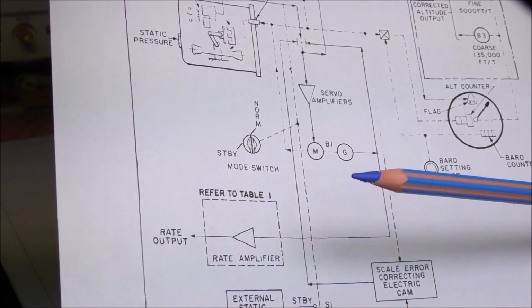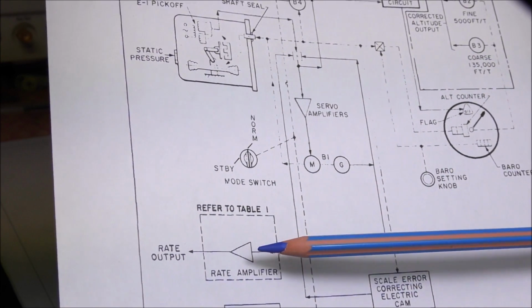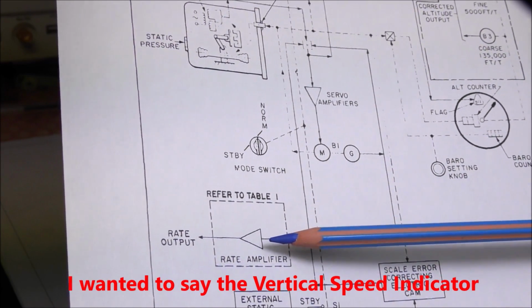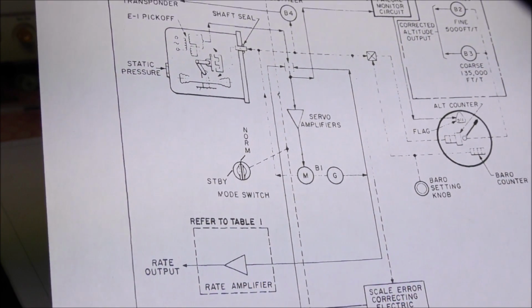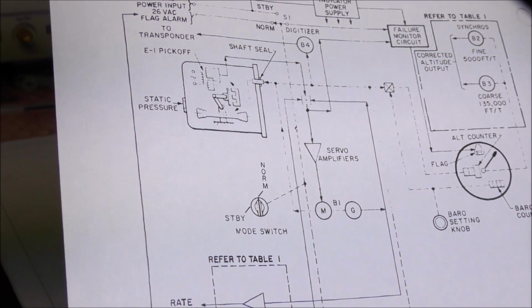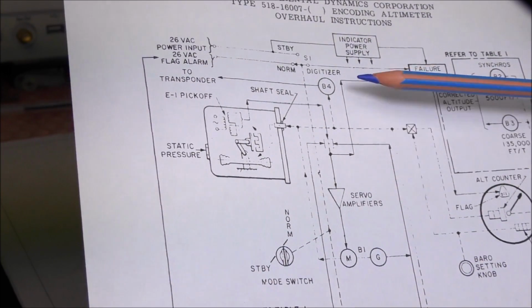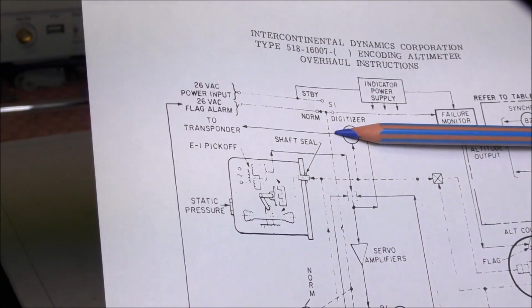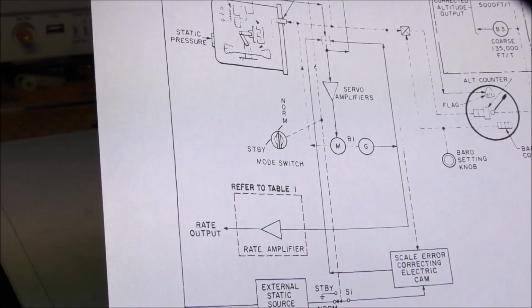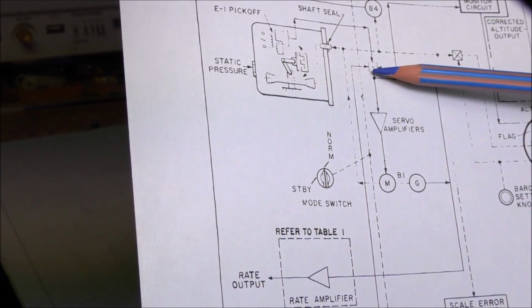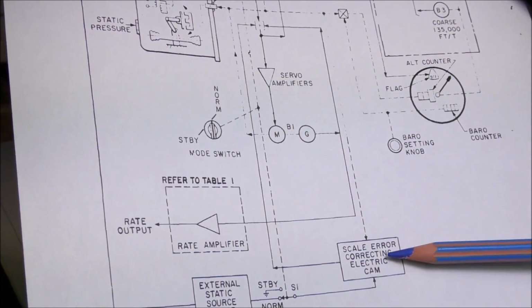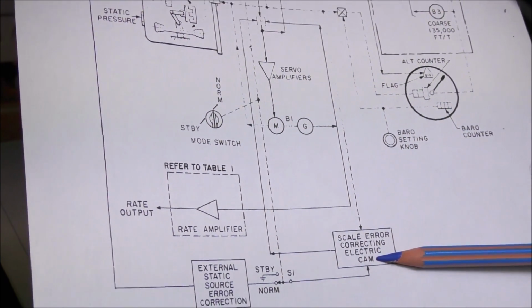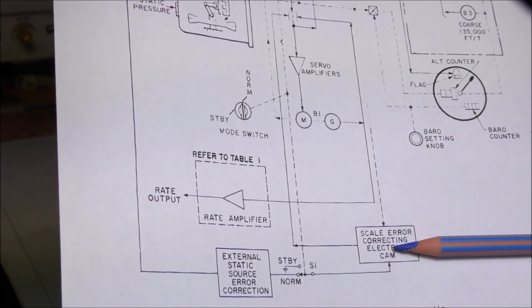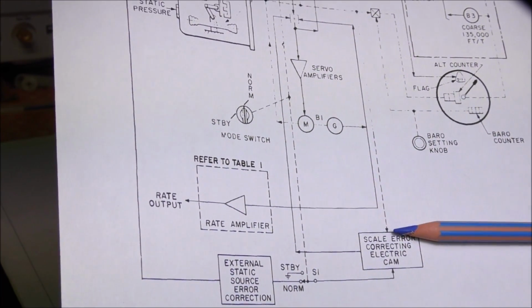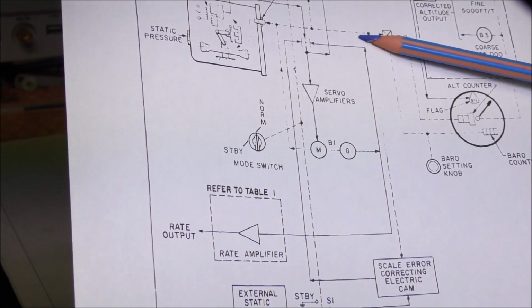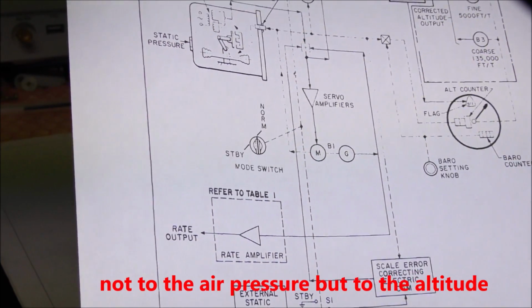So it will be possible to test this output using the altitude rate I have described in my previous video. It will be also possible to test the digitizer using the small instrument I have designed several weeks ago. At the input of the amplifier here we have a third signal. So this signal comes from the scale error correction electric cam. So this is actually a potentiometer with the different taps. So this permits to have a linear variation of the angle of the shaft here relative to the altitude, which is measured by the transducer.